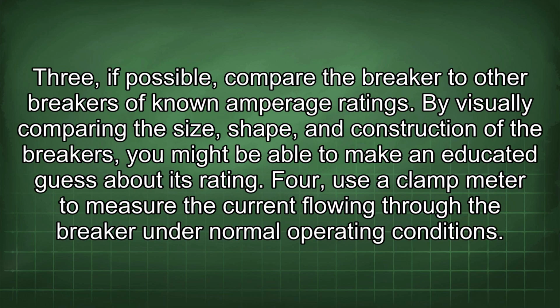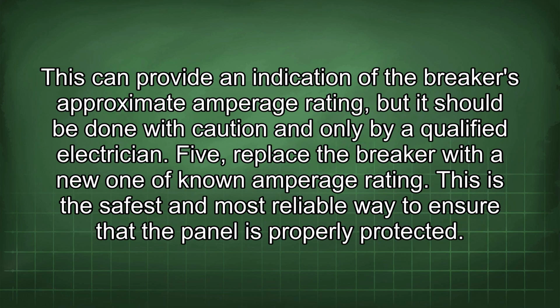3. If possible, compare the breaker to other breakers of known amperage ratings. By visually comparing the size, shape, and construction of the breakers, you might be able to make an educated guess about its rating. 4. Use a clamp meter to measure the current flowing through the breaker under normal operating conditions. This can provide an indication of the breaker's approximate amperage rating, but it should be done with caution and only by a qualified electrician.